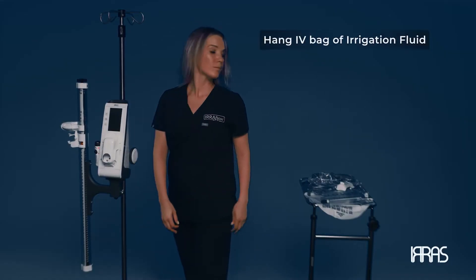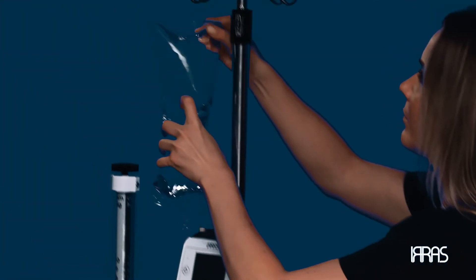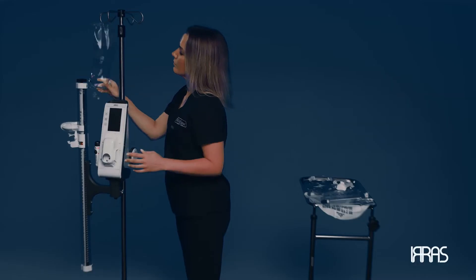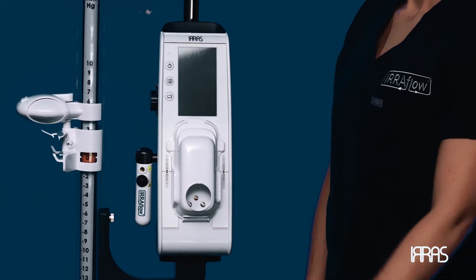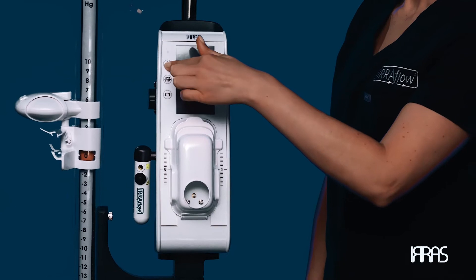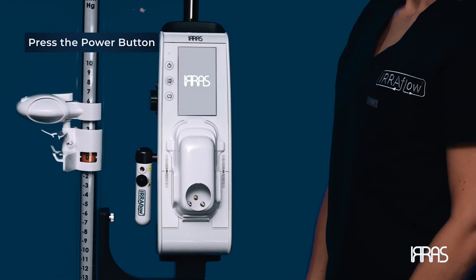Hang the IV bag of desired irrigation fluid. The indicated irrigation fluids for use with the IRRAflow control unit are normal saline and lactated Ringer solution. Once positioned on the pole and plugged into an approved electrical outlet, press the power button and turn on the control unit.